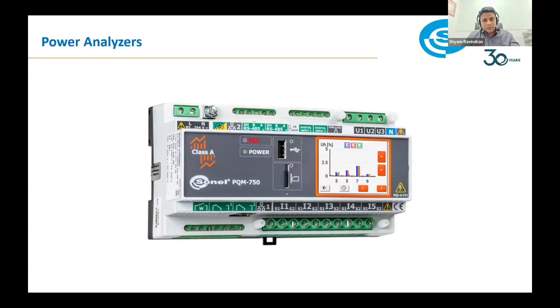For example, if you say your TDD is beyond the percentile value mentioned in IEEE 519, and you want to take this discussion with the utility, unless there is certified equipment, this cannot be upheld, because any equipment can generate any data. If you see from the hardware perspective, any analyzer only has voltage and current inputs. Every other parameter is mathematically calculated or generated, so unless we have proper certification behind it, this cannot be legally emphasized.